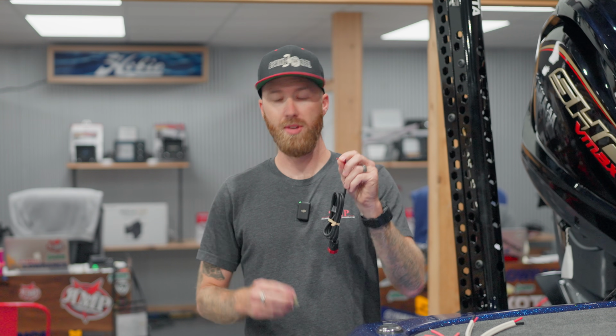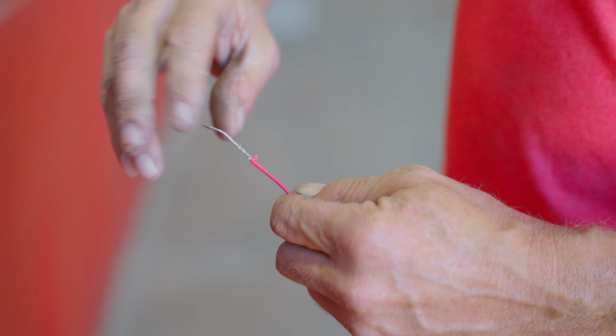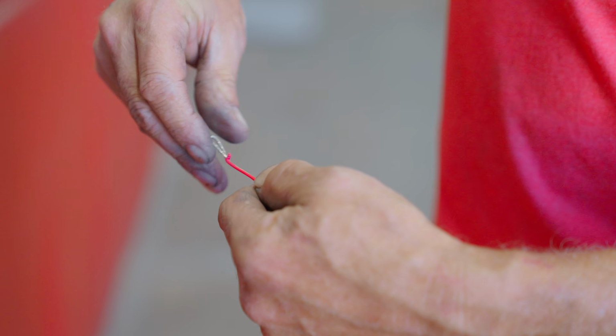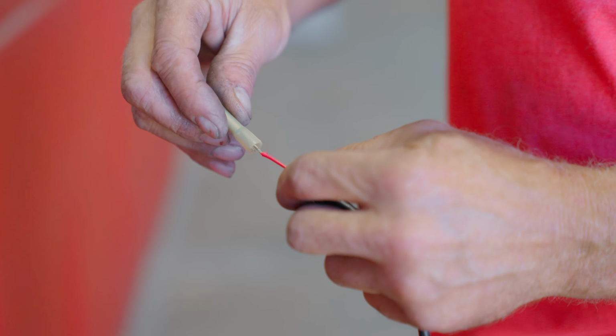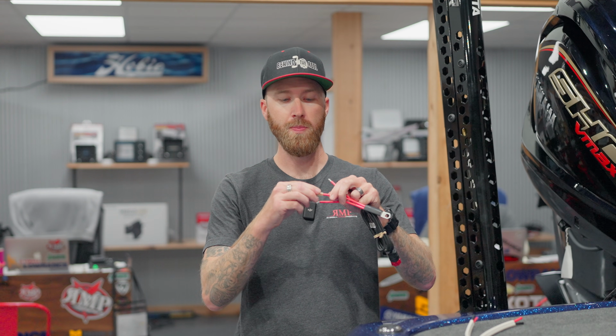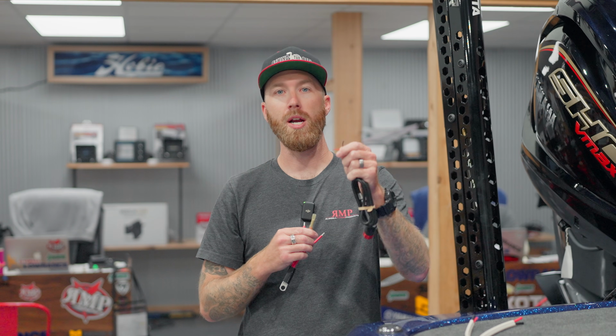Okay, one quick install tip for running the dedicated power. You've typically got a much smaller gauge wire coming out of the unit. You're seeing these smaller, 14, 16 gauge wires, and we're connecting it to a 10 gauge positive connection, right? So what we're doing is using these 10 to 12 gauge heat shrink butt connectors. Once you strip that smaller gauge wire, we'll double it up so you still get a good bite on this bigger butt connector. This bigger connector obviously fits the 10 gauge wire really well, but you need to double up your wire on the smaller gauge side to get a real good bite.